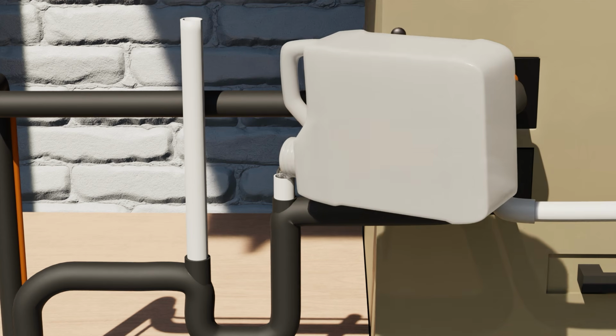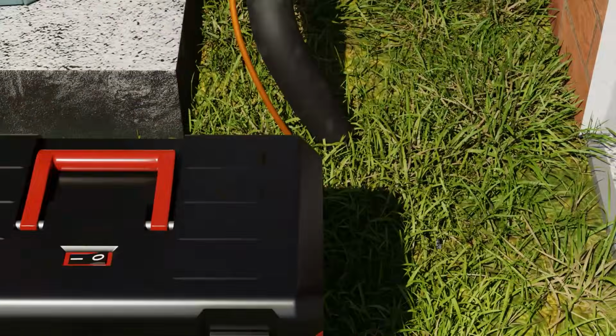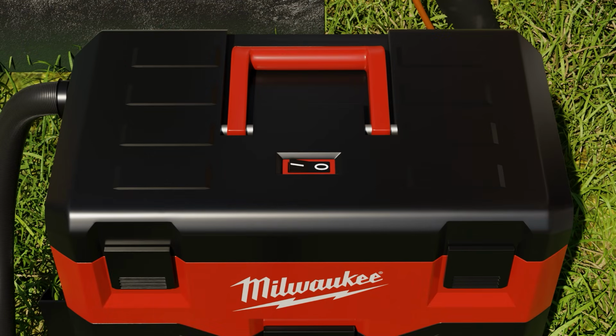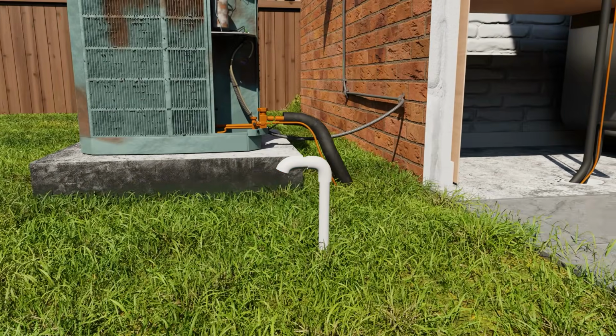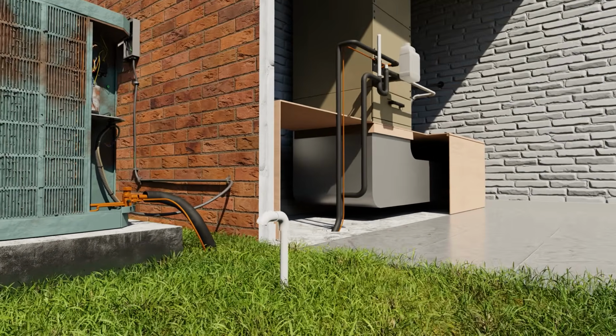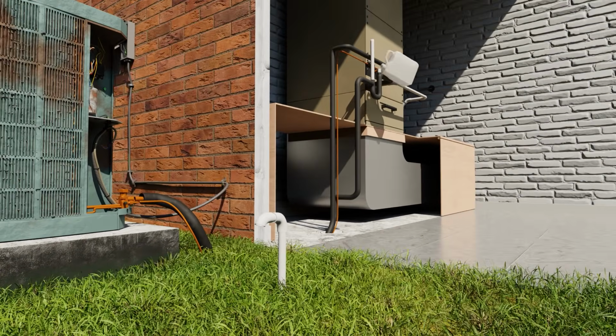There are some alternative methods we can use, such as nitrogen or CO2. But even if you use those methods, be sure to finish up using this procedure of flowing water through with a shop vac. Always refill the trap when you're done and make sure the water pours out freely. Sometimes this may be hard to observe, and so you could simply put a dry rag or a cup underneath the drain in order to ensure that water did come out when you look again outside.